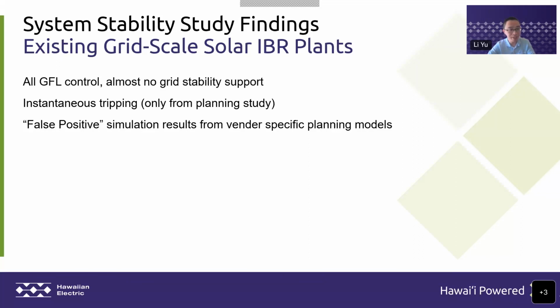Also, in the planning study, we see that there's a potential risk of instantaneous tripping because of either zero time delay voltage tripping or frequency tripping. I think this is similar to what NERC found in the mainland large-scale PV plant tripping report. From the models we put into the study, we see very different results.